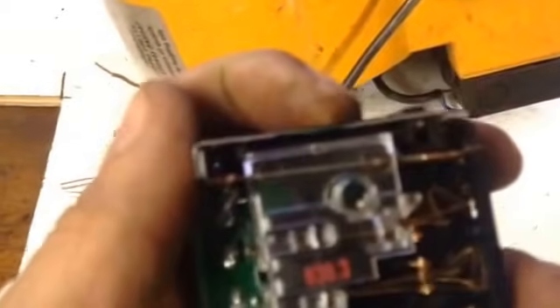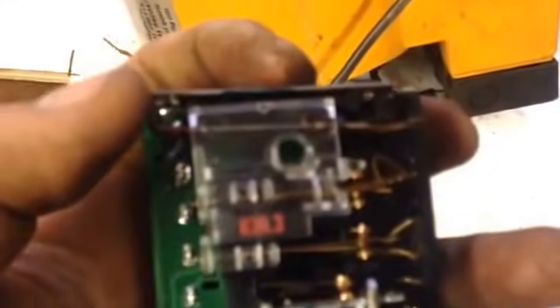Right, interesting how these things work. What they do is they have a bimetallic strip at the top here, and when you first turn it on, this bimetallic strip starts to move and drag a series of contacts on. So the first thing it'll do is drag on the fan, then it'll drag on the spark. So it's just moving up, contacting more and more switches all the time - click, click, click. You can look to see whether things have gone wrong in there, but to be fair, good luck.